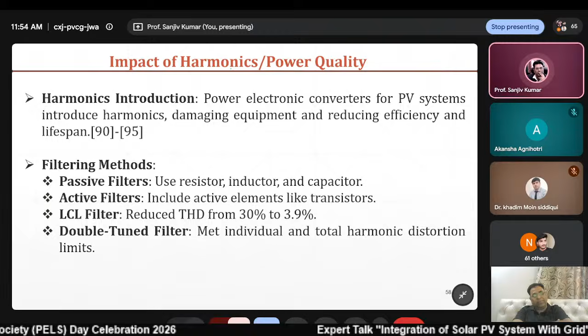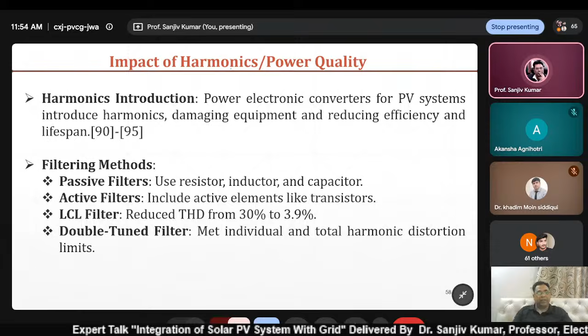So you have to use some damping equipment or filters. It could be an active filter, a passive filter, or an LCL filter, which reduces the THD from 30 to 3.9, meaning it reduces the lower order harmonics. But at the same time, you should think over the size of the filter needed.